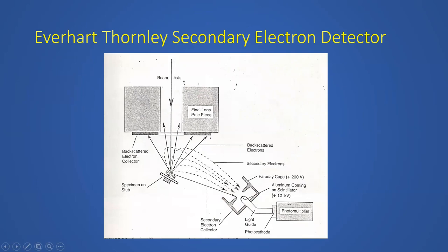As a result of this interaction, you have these signals. You have backscattered electrons, which are going to this detector. You have a backscattered electron detector here. Then you have your secondary electrons, for which you have a dedicated secondary electron detector. These are guided down to the photocathode and photomultiplier tube, PMT, and they are processed, and you can see your image on the screen here. So this is how the detectors work, and their locations around the specimen in the chamber.